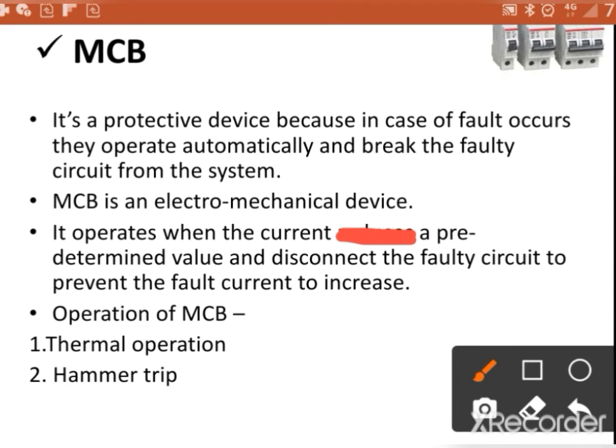MCB has therefore replaced fuses and can be installed in a consumer's distribution board or panel. The main advantage of MCB is that it is more accurate, and whenever overload occurs, it provides protection to the system. The MCB operates on 5% to 20% of excessive overload. There are mainly two operations of MCB. First one is thermal operation and second is hammer operation.